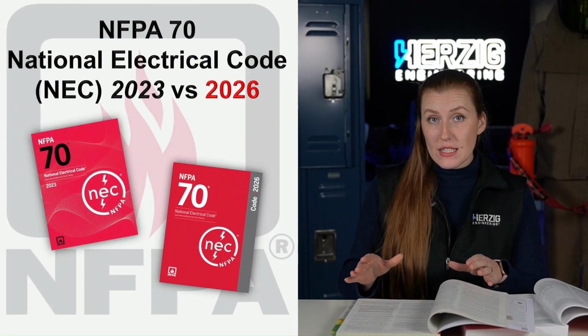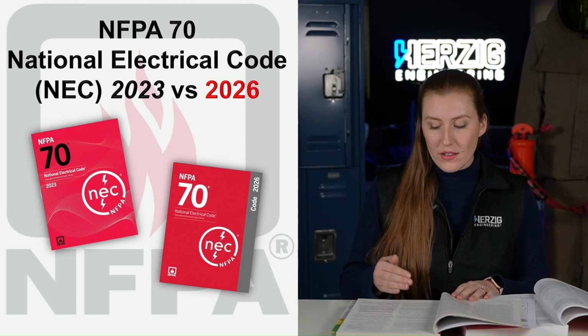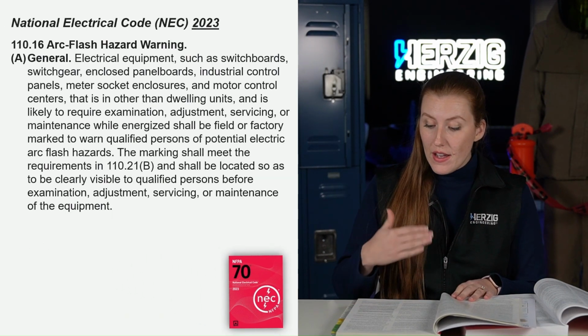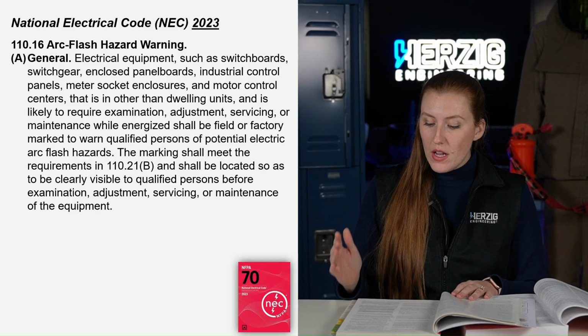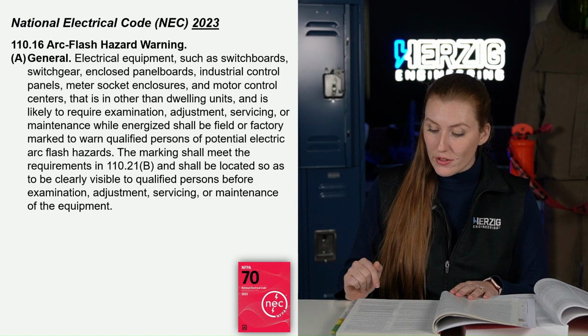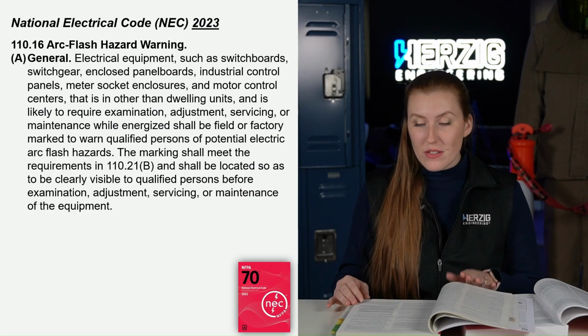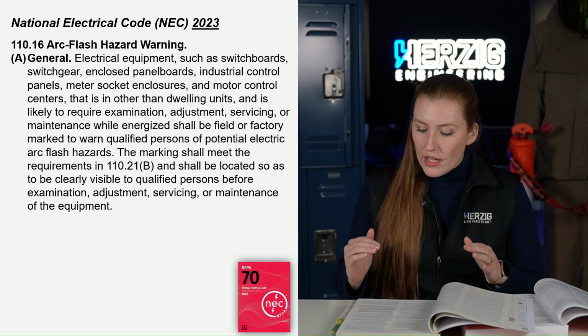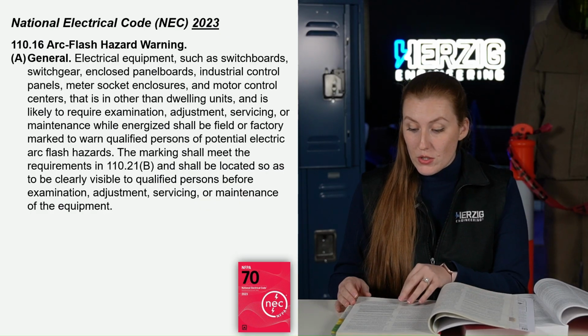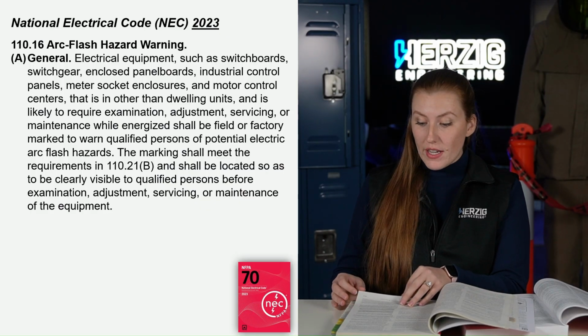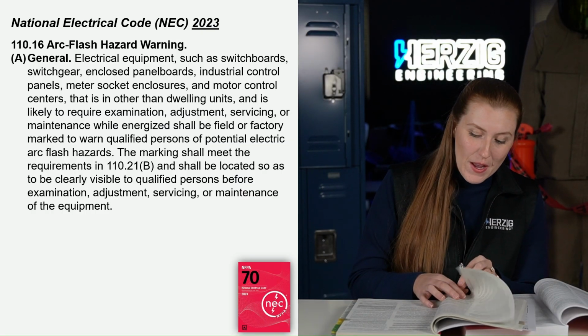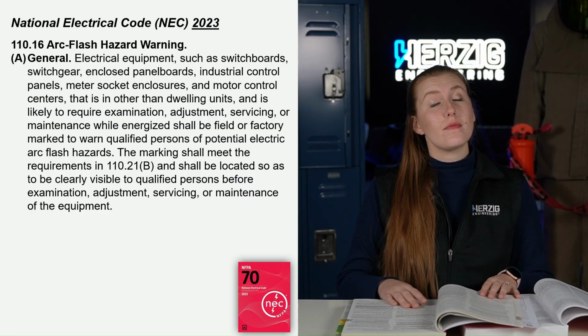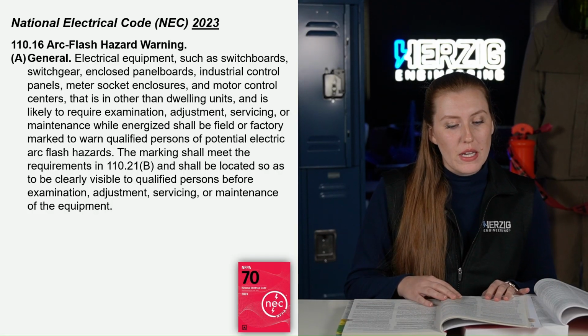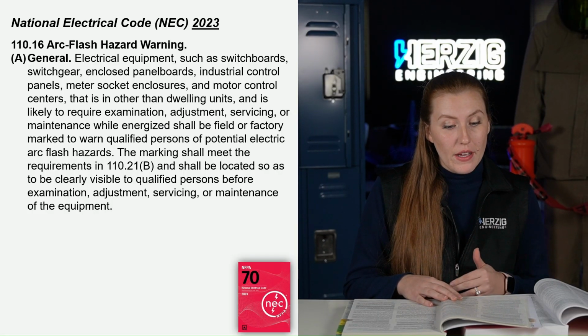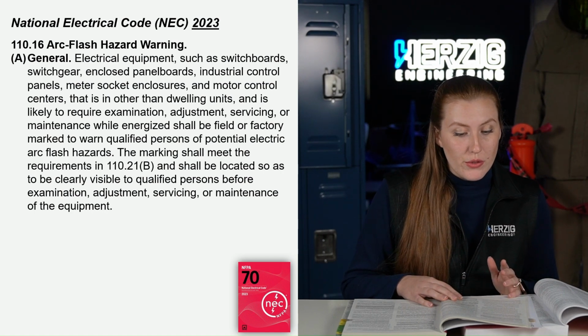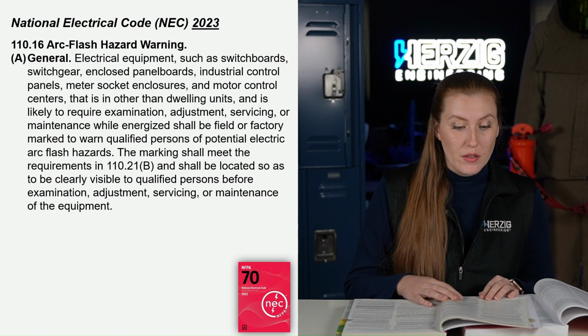So in 110.16, the arc flash hazard warning in the 2023 National Electrical Code said electrical equipment such as switchboards, switchgear, enclosed panel boards, industrial control panels, meter socket enclosures, and motor control centers in other than dwelling units that are likely to require examination, adjustment, servicing, or maintenance while energized shall be field or factory marked to warn qualified persons of potential electrical arc flash hazards. Long sentence there. And of course, it should meet the requirements in 110.21(B) and shall be located as to be clearly visible to qualified persons before examination, adjustment, servicing, or maintenance of the equipment.